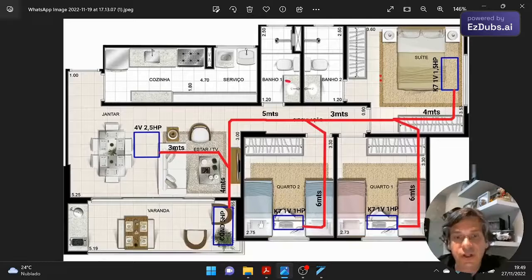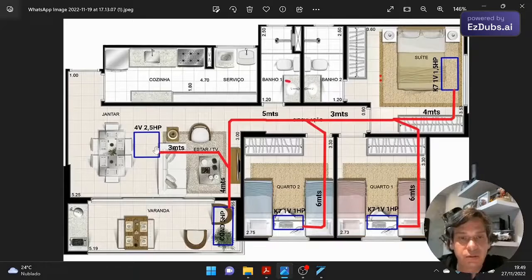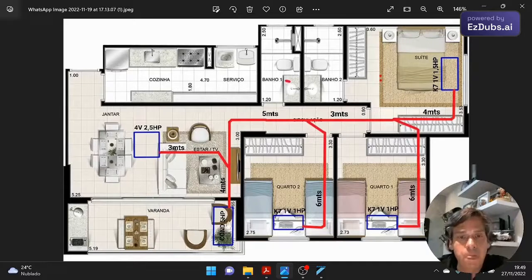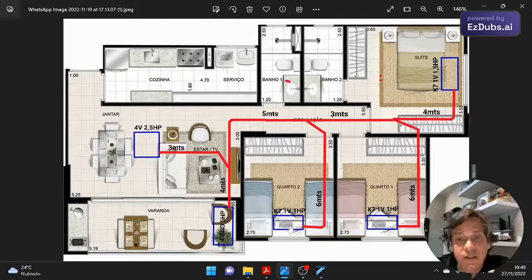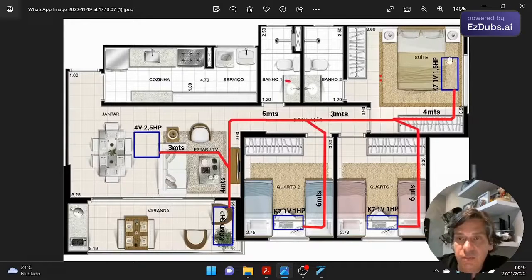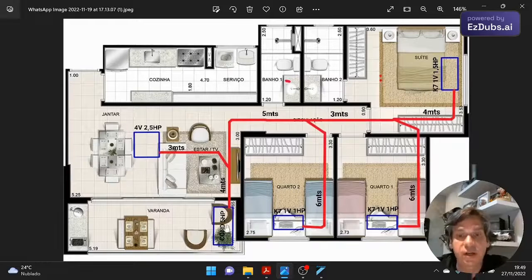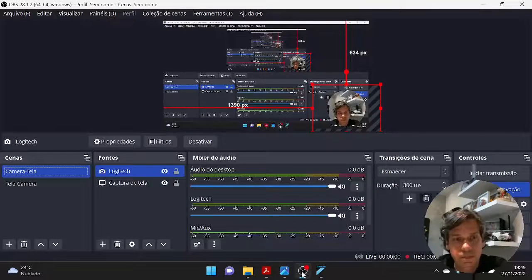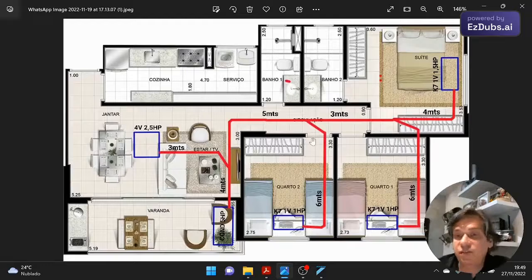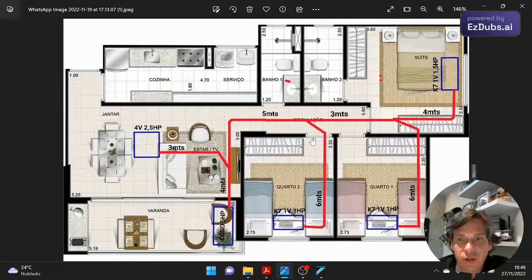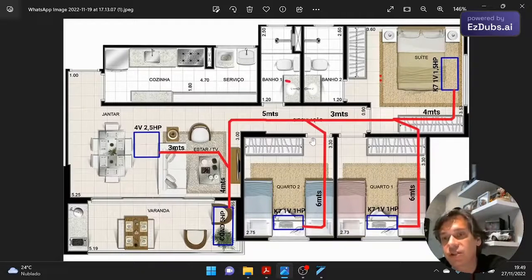As I told you, we are going to make the system very small because that is how we have to treat it initially. So our system will be made up of four evaporators, a small apartment here, a 2.5 HP evaporator in the living room, a 1 HP cassette in each of the bedrooms, a 1.5 HP cassette in the suite. The condenser we chose is a 5 HP condenser.